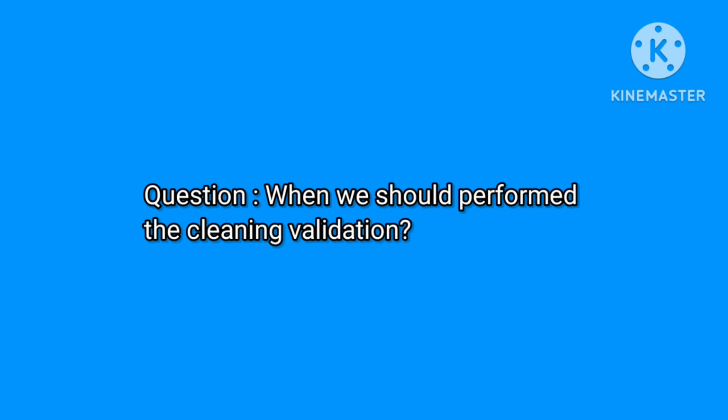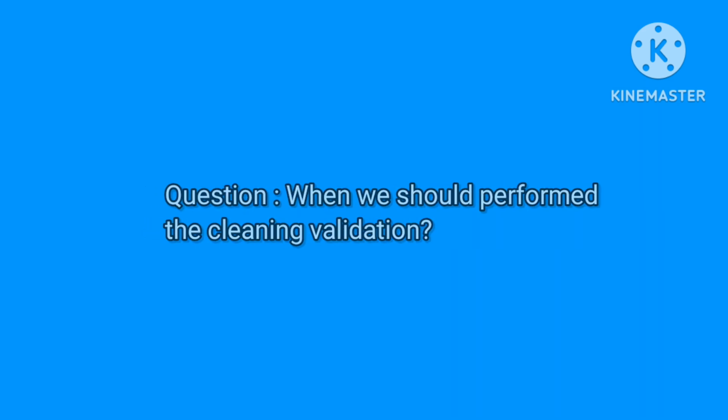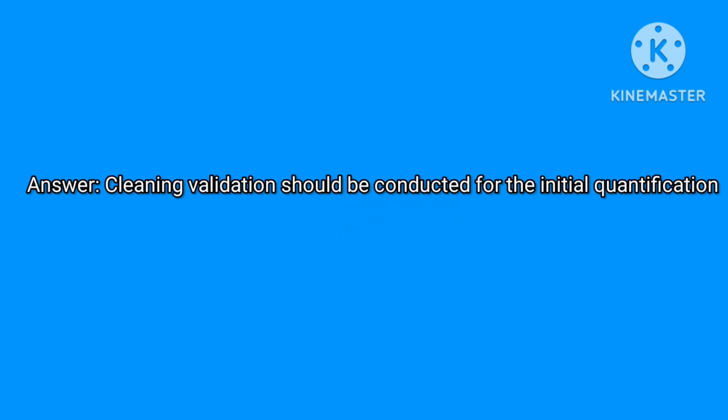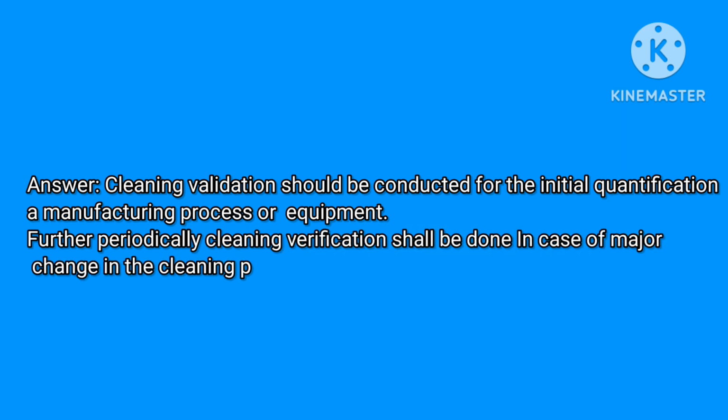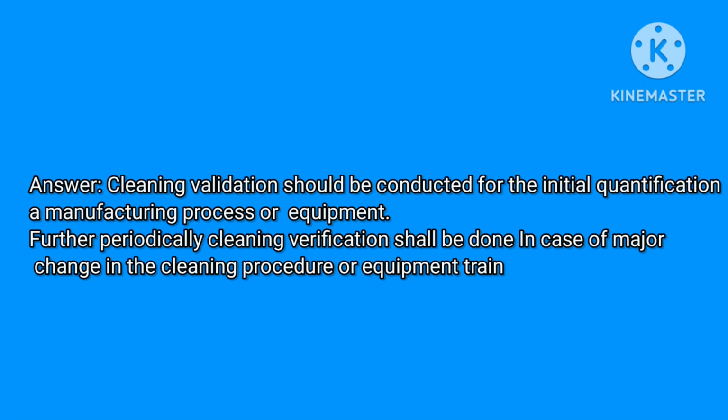Next question: when should we perform cleaning validation? Answer is: cleaning validation should be conducted for the initial qualification of a manufacturing process or equipment. Further, periodically cleaning verification should be done in case of a major change in the cleaning procedure or equipment.